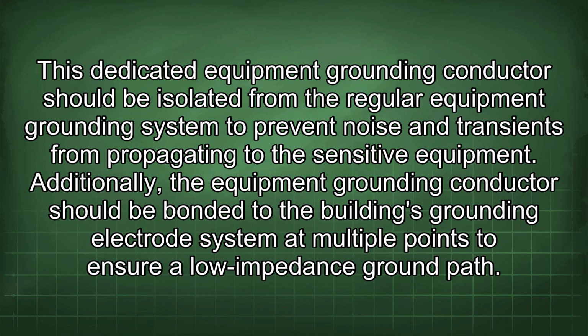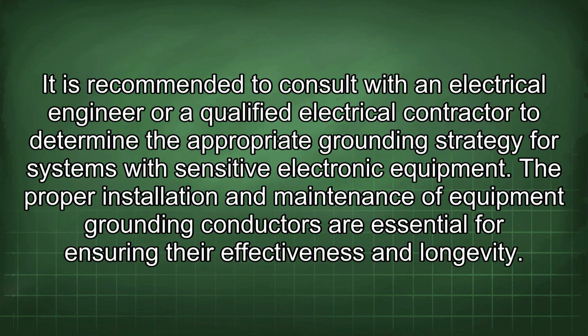Additionally, the equipment grounding conductor should be bonded to the building's grounding electrode system at multiple points to ensure a low impedance ground path. It is recommended to consult with an electrical engineer or a qualified electrical contractor to determine the appropriate grounding strategy for systems with sensitive electronic equipment.